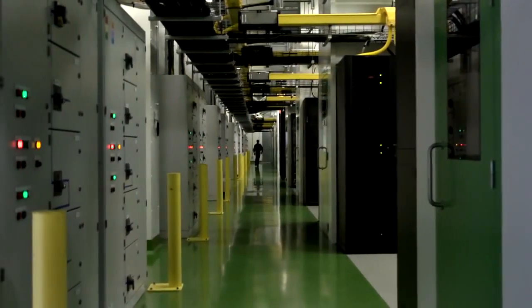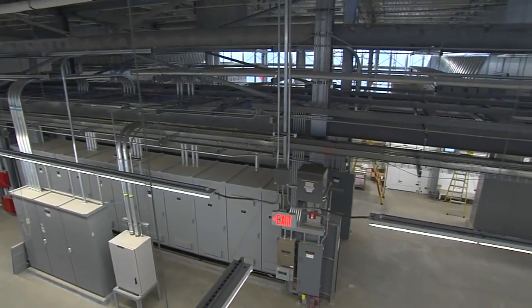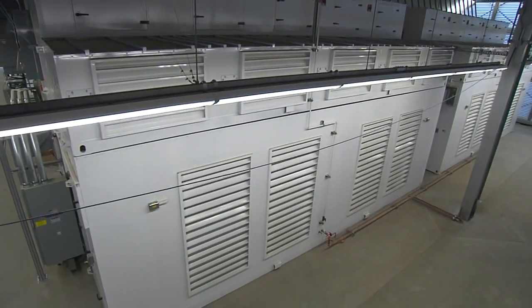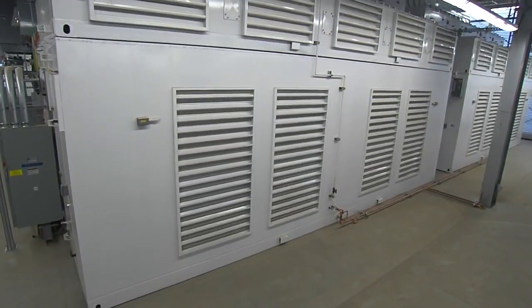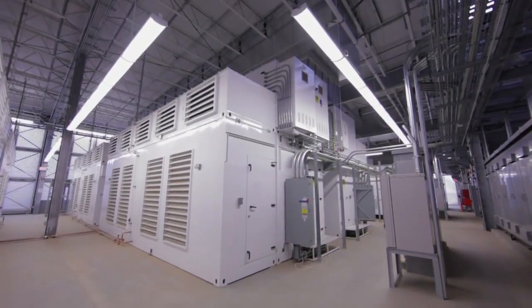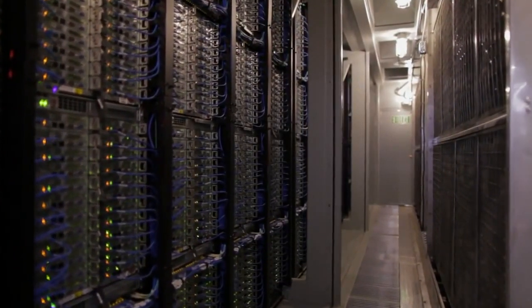In 2010, we began to build our first Generation 4 data center design, building on the Dublin experience of using air-side economization into a truly modular design. This technologically advanced facility challenged every industry design standard to significantly reduce water and power use. Our Generation 4 facility utilizes air-cooled IT pre-manufactured components, or IT packs — pre-assembled, plug-and-play modular components that can be manufactured in many locations through a dynamic supply chain of globally distributed vendors. They use recyclable materials such as steel and aluminum, which are then shipped on-site and assembled.